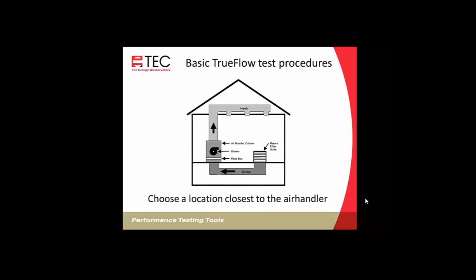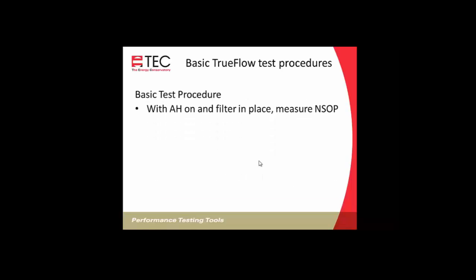So the basic procedures, you want to get the most accurate reading, you want to be at the location closest to the air handler. So if there's a filter grill right at the air handler, that's a preferred location to, say, a return filter grill, if you have the option of the 2. The basic test procedure, with the air handler on and the filter in place, will measure the normal system operating pressure, and you'll see that abbreviation NSOP a lot throughout this presentation. That's the normal system operating pressure.